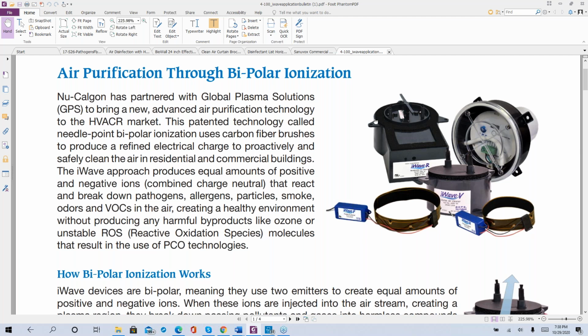the fan is running. But you do have to be careful if you've got an ECM fan motor, and these are going in furnaces, they're going in fan coils, they're going in anything that has an ECM fan motor, you're going to get that varying voltage and amperage. And so you can't really tie the I-wave to that same power going to the fan motor. So instead, we would put the transformer somewhere where it can be interlocked, and then put a variable ECM or a current transformer that you can adjust that will sense very, very low amp draw. And then that becomes your interlock.